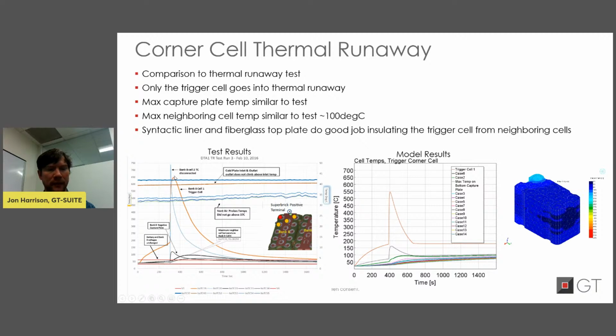That cell temperature spikes dramatically, but neighboring cell temperatures, the maximum is much cooler and never goes into thermal runaway. And so you can see these very similar trends in a predictive model utilizing the same test procedure, where the single corner cell gets heated to the point of thermal runaway, but the neighboring cells are not affected because the insulation layer is doing its job.